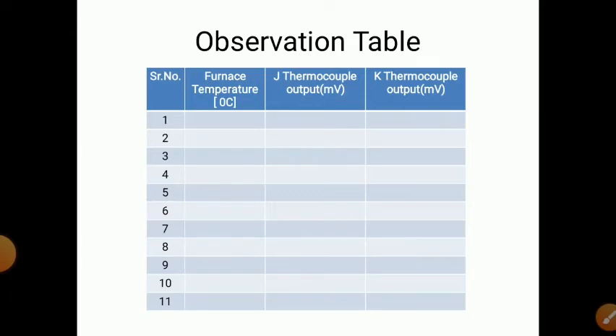The observation table has two columns: furnace temperature in degrees Celsius, and thermocouple output in millivolts for J type and K type. As temperature increases, voltage also increases. Readings are taken at 10-degree Celsius intervals — at 10, 20, 30, 40, 50, 60 up to 100 degrees Celsius — noting voltage for both J and K type thermocouples.